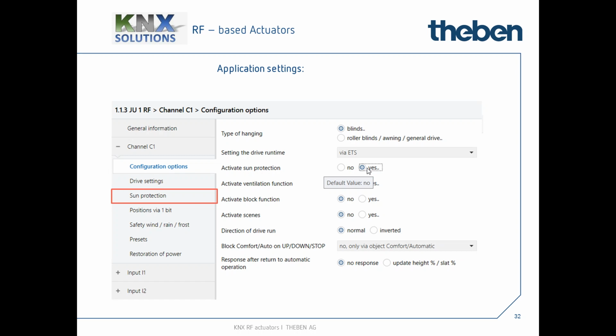Vice versa, for the hot summer seasons we need a kind of cooling support. If outside the sun is heavily shining and inside the room is quite warm or slightly overheated with nobody present, the blinds run totally down, closed, to keep the warmth and sun out so as not to heat up the room tremendously. When somebody enters the room, the slats open and lift a little, depending on presets, and these slats are adjusted by the position of the sun - active heating and cooling support from an intelligent shutters and blinds actuator.